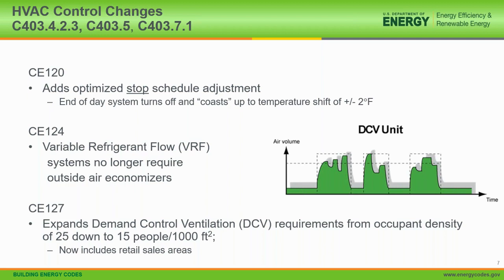Variable refrigerant flow systems no longer require outside air economizers. You might be aware that there is an exception from economizers for smaller fan units. However, in the IECC, there is a maximum limit on how much cooling capacity there can be in the building without economizers, and so VRF systems were running afoul of that limit. This basically allows them to not have outside air economizers, and they make up for it by lower fan power and higher operating efficiency.